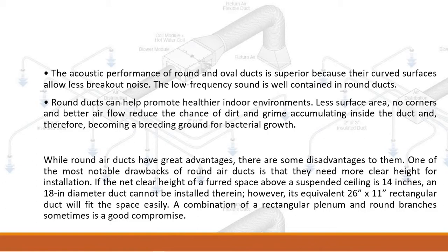While round air ducts have great advantages, there are some disadvantages. One of the most notable drawbacks is that they need more clear height for installation. If the net clear height above a suspended ceiling is 14 inches, an 18-inch diameter duct cannot be installed therein; however, its equivalent 26x11 rectangular duct will fit easily. A combination of a rectangular plenum and round branches is sometimes a good compromise.